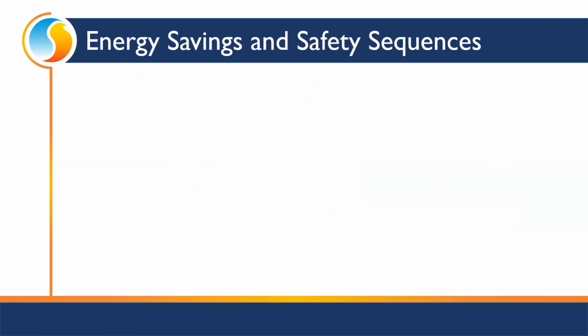So with some of our energy savings and safety sequences, we can limit the available set points that they can adjust on the wall modules. Just because there's a sticker that says from 59 to 86 on there, we're going to choke that down and they get, say, 68 to 73. Okay, and that's all in the software. They can't override that.